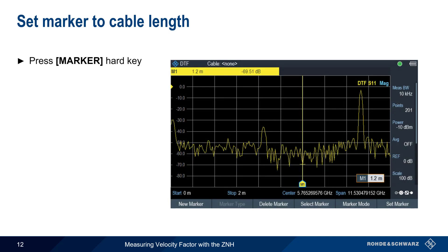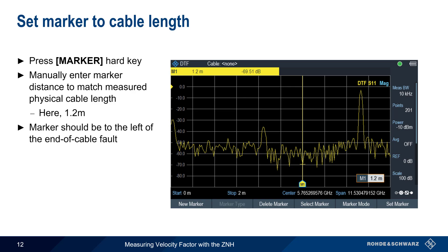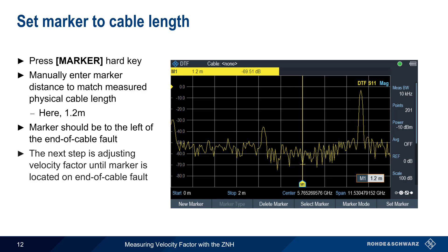Now we need to place a marker using the Marker hard key. After creating a new marker, manually enter the distance to match the measured length of the cable, here 1.2 meters. Since our manually configured velocity factor of 1 is clearly too high, this will cause the marker to be to the left of the end-of-cable fault. All that's required now is to adjust our manually configured velocity factor until the marker is on top of the end-of-cable fault.